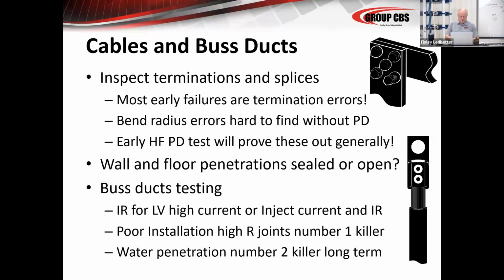And a good PD test will get you a long ways toward determining if these cables have been overbent and there's been radius errors or any of that sort of thing. Bend radius errors are hard to find without PD. A lot of the failures that I've seen over the last 45 years in cabling systems have been scuffed up and torn cables being pulled through bend radiuses too tight, and the manufacturers say don't do that, and they do it anyway. And it doesn't show up until there's a little moisture induced into the situation. Then you've got a real problem. But a PD test will pick that up because it'll pick up a difference between a drain wire that has been damaged or stretched or turned.